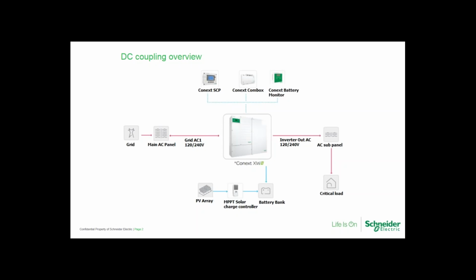And I'd like to take a moment to mention that that's a very important point related to your battery bank sizing, because depending on the capacity of the battery, you may or may not be able to accept the maximum current from your array as designed. So that's your primary consideration: is your bank appropriately sized to accept all of the current from all of your PV sources that are being supplied through the charge controllers?